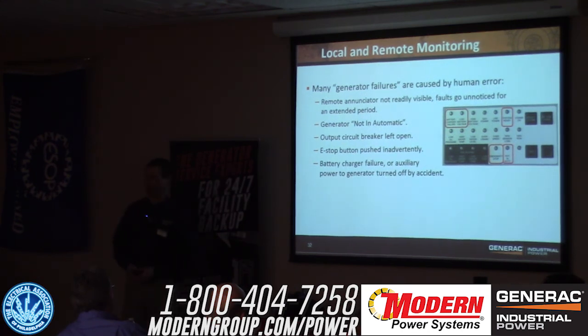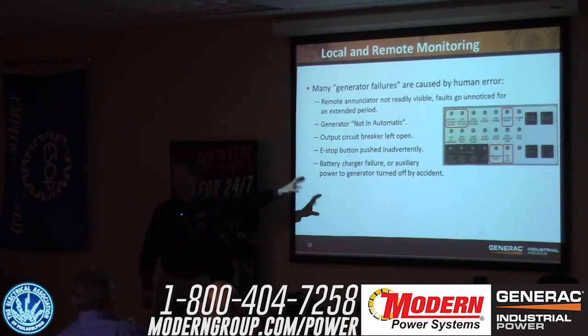Somebody turns the accessory power off to the gen set—it happens. Somebody flips that breaker down in the distribution panel and kills the power to the generator set. Battery charger stops, block heater stops—all this is going on, and if nobody notices it, that machine is not ready. It's not going to do its job when it's called upon.